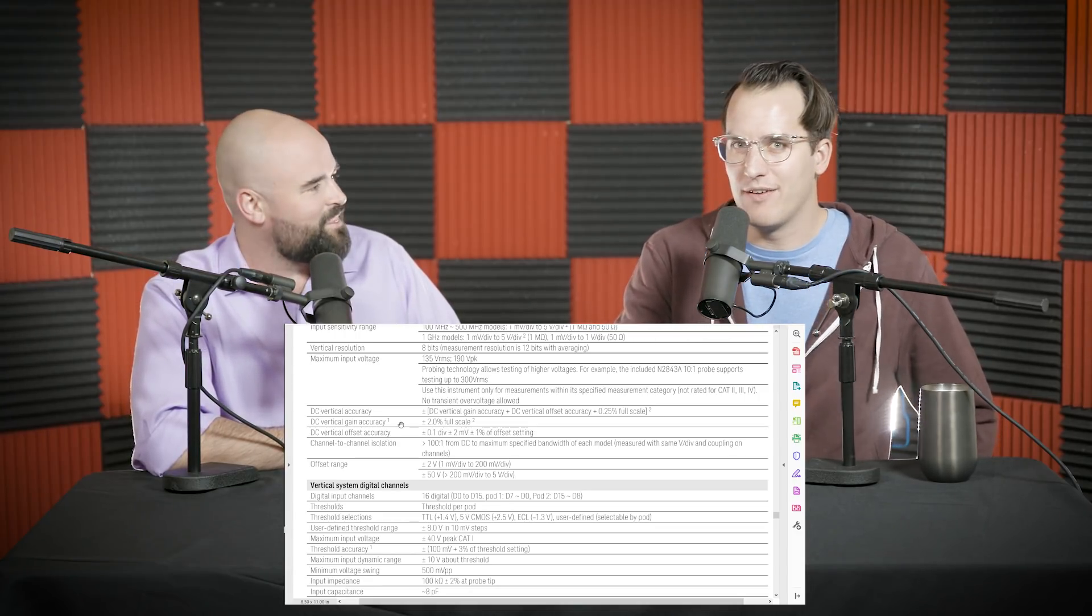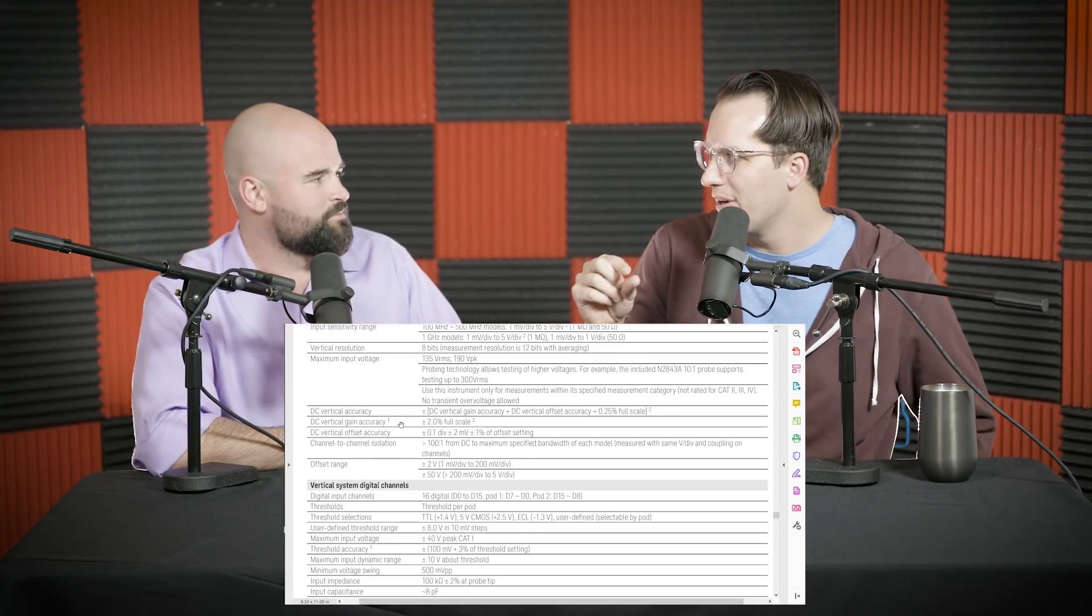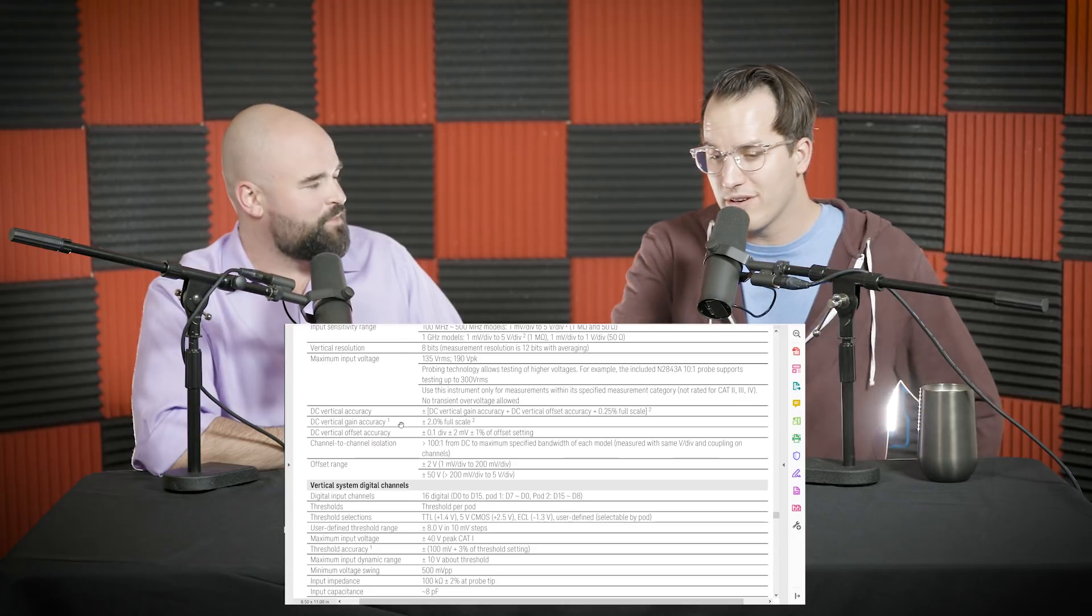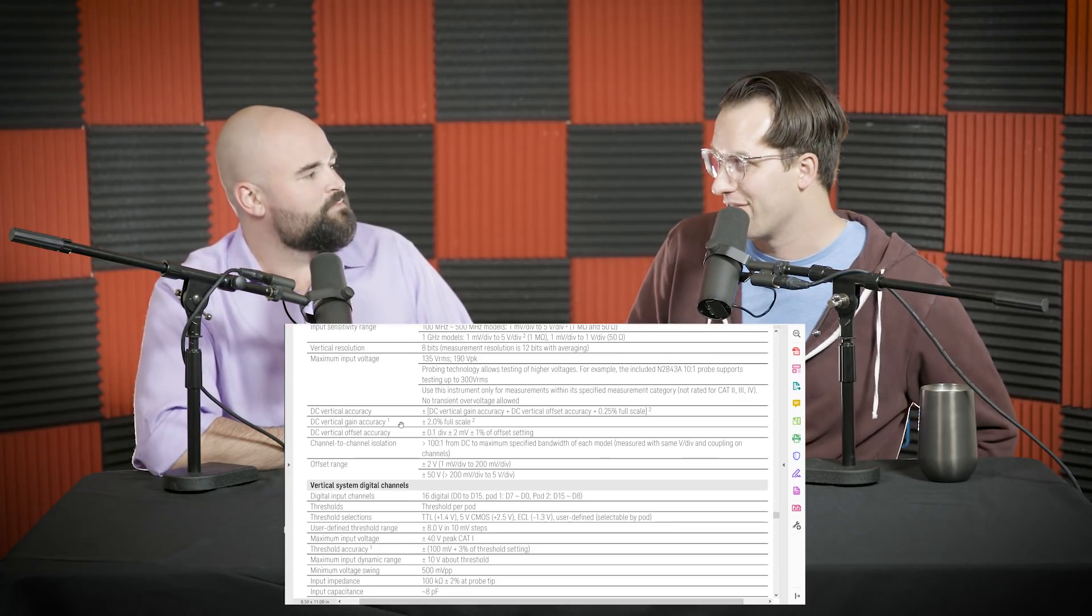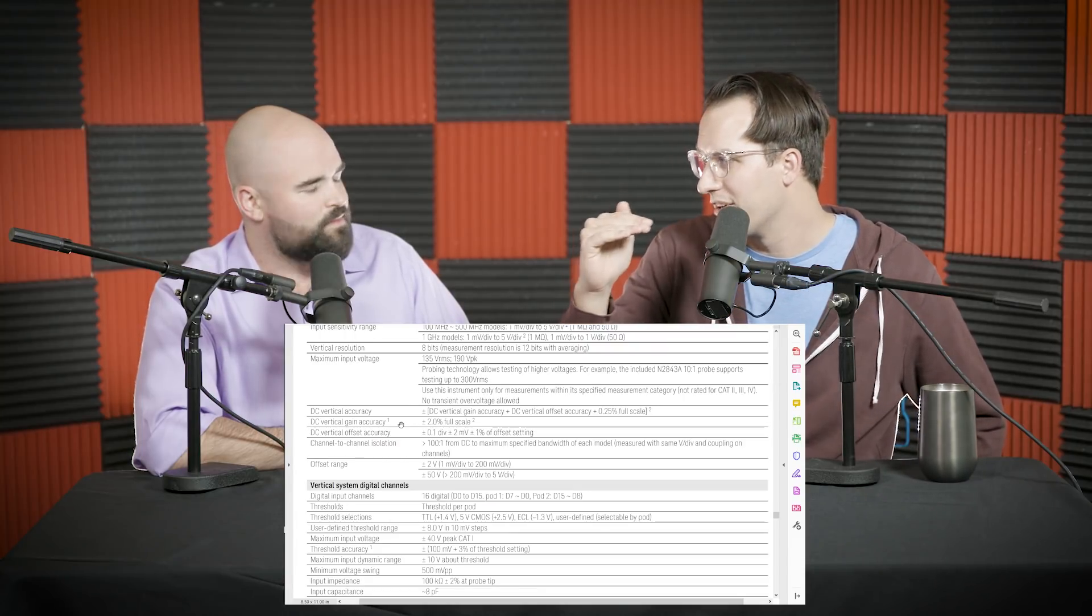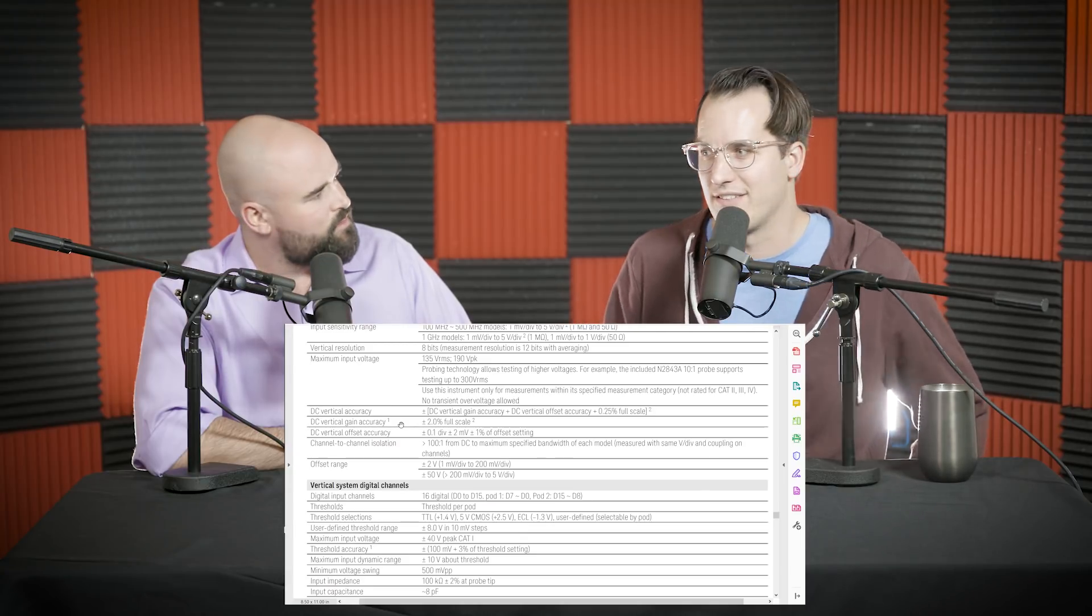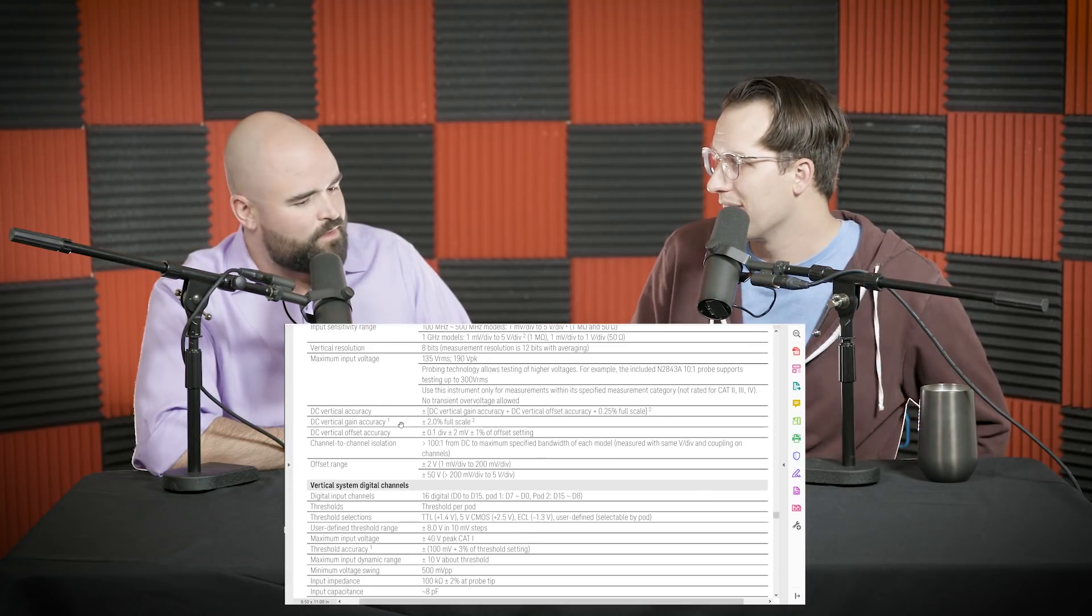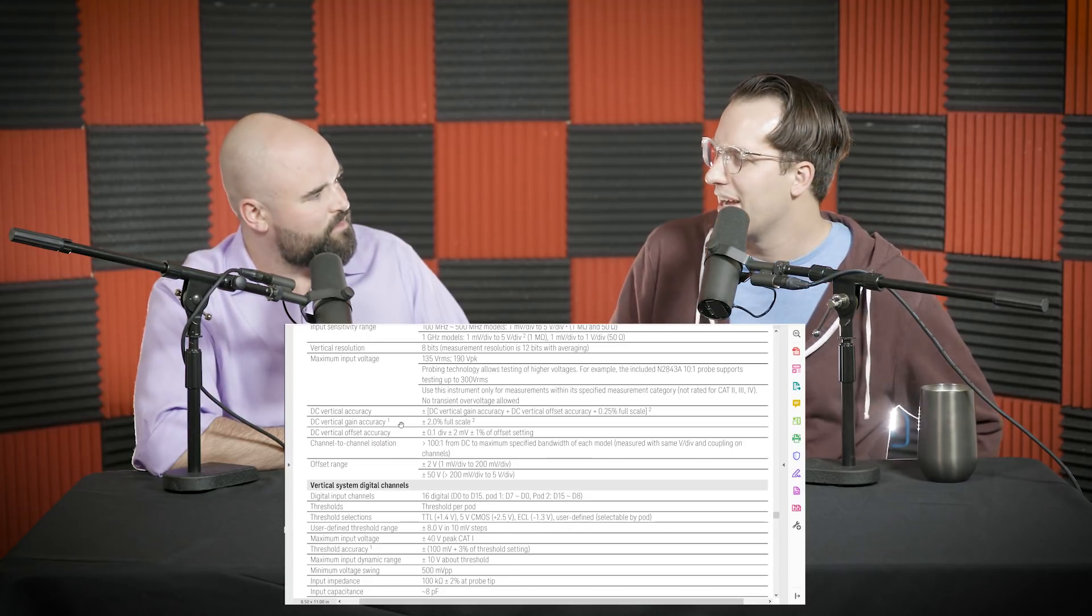If you need to measure DC accuracy, super fine tuned, the oscilloscope is not the tool for you. You go look at all these oscilloscope data sheets and they're all going to say DC Vertical Gain Accuracy. And that means if I plug in a two volt DC signal, how close am I going to actually get to two volts? And AC, it's usually pretty good. You can look at the frequency response and see that it's fine. But the warranted spec is DC Vertical Gain Accuracy.